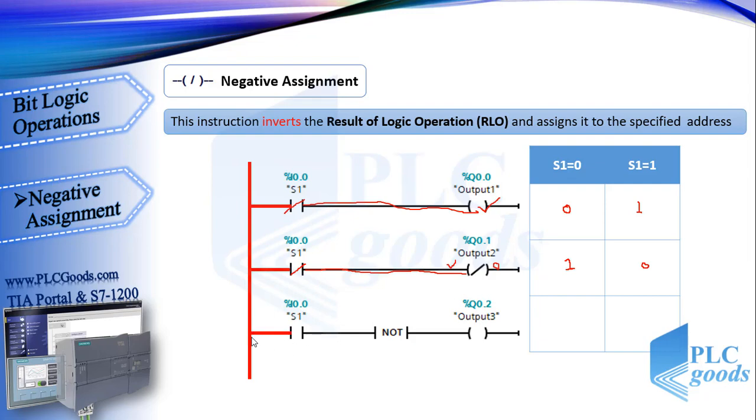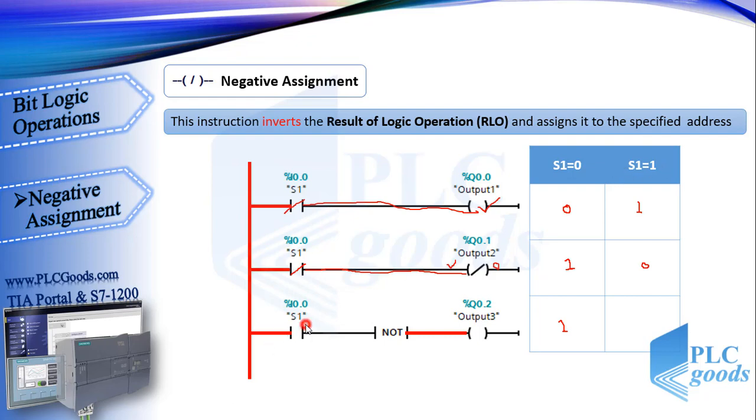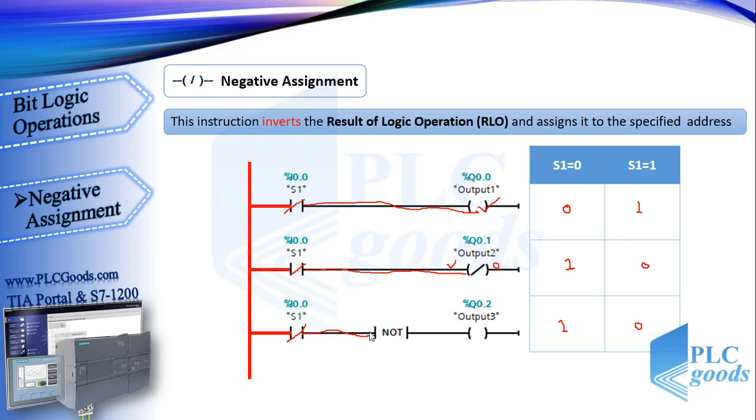Now see the last line. When S1 is inactive, the virtual power can't reach to the NOT instruction. We've seen this instruction inverts the power state. So after that, we have virtual power which can turn on output three. In the other state, when S1 is activated, virtual power reaches the NOT instruction which makes we don't have virtual power after that. So the third output will be off. As you see, second and third line have same performance. So we can have negative assignment logic with a NOT and an assignment instruction.